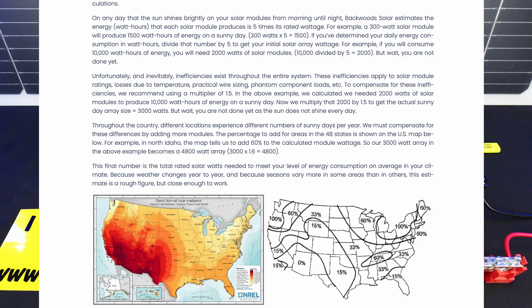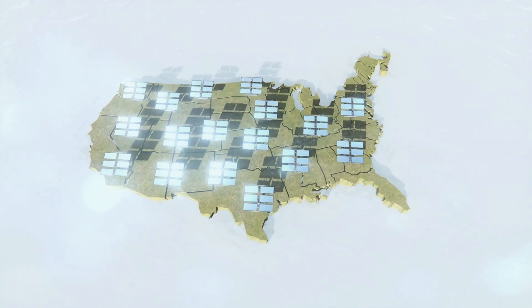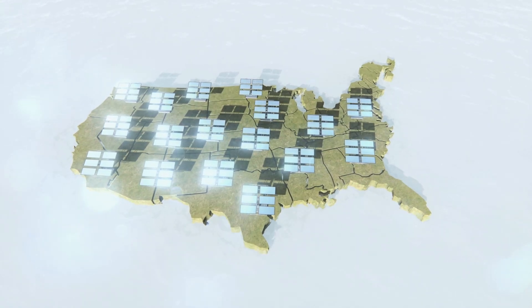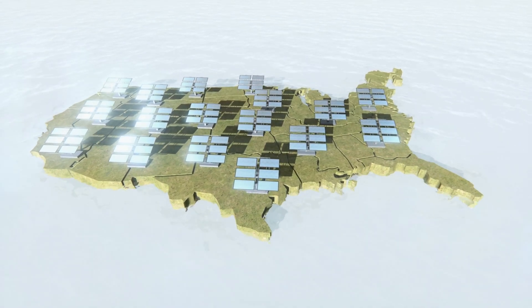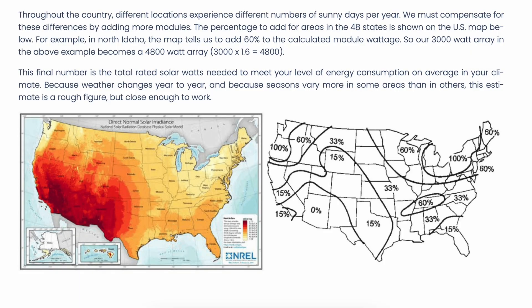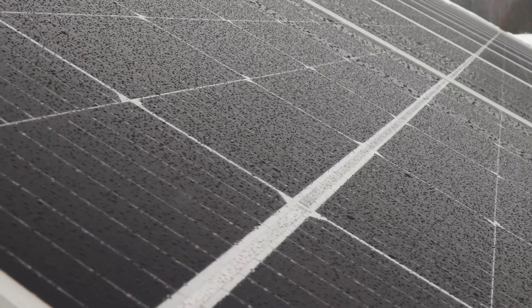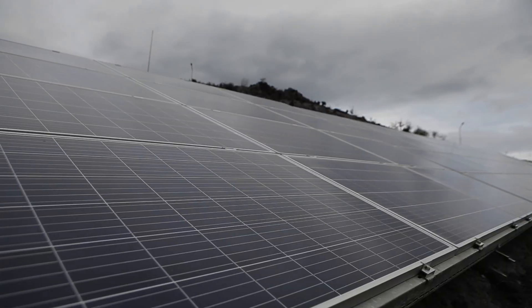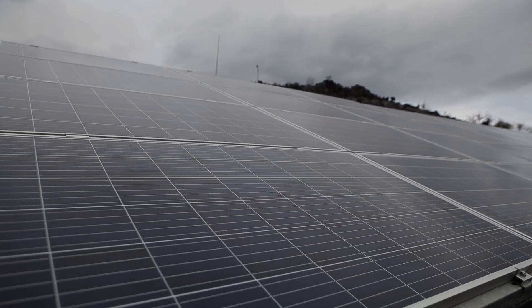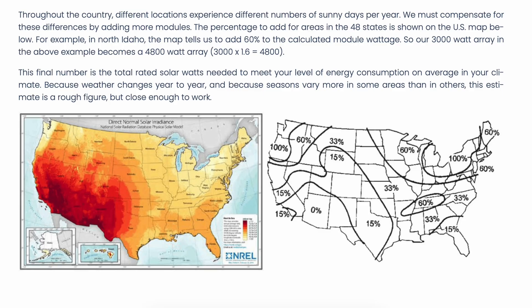However, we have one other factor we need to take into consideration: regionality, and with that some seasonality as well. So here in our example, if we have that 3,000 watt array and we're here in North Idaho, we're going to add 60% of loss to that, assuming relatively poor winter conditions and short winter days. So if we take that 3,000 watts and multiply it by 1.6, we're going to find out that to produce that 10 kilowatt hours here in North Idaho, we would need an array size of about 4,800 watts.